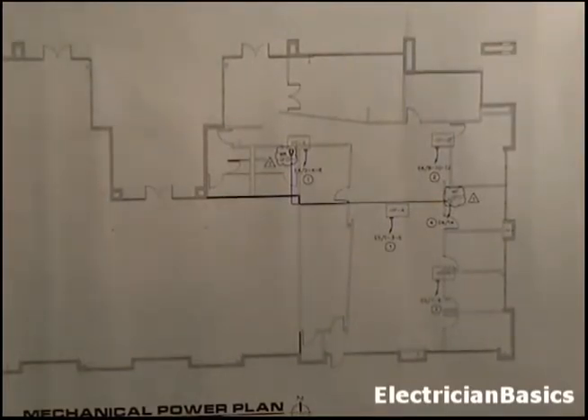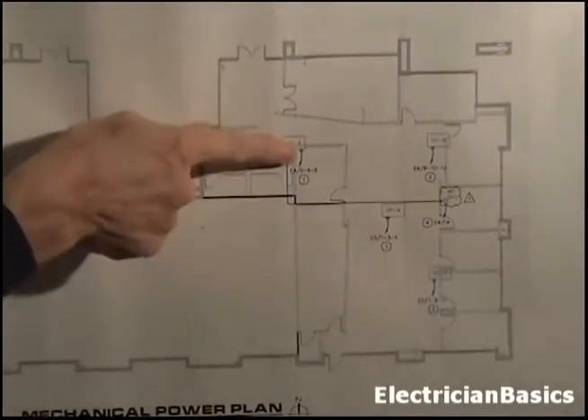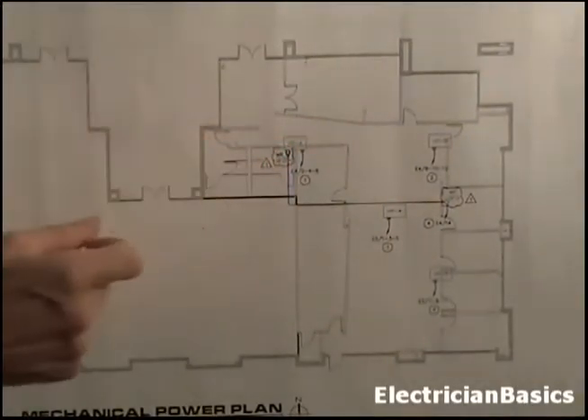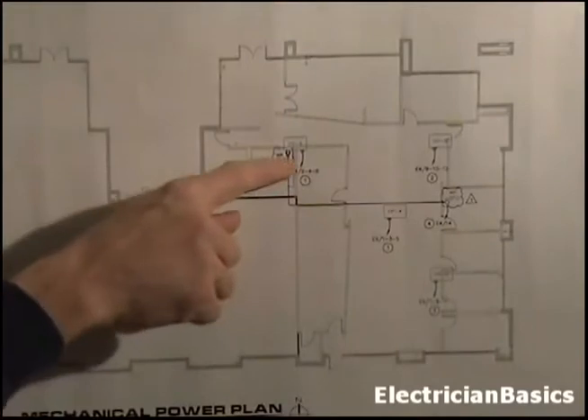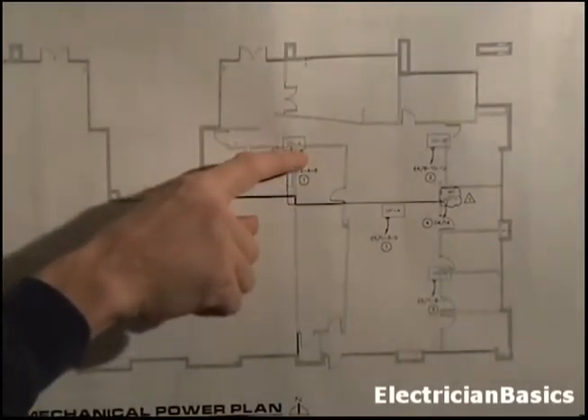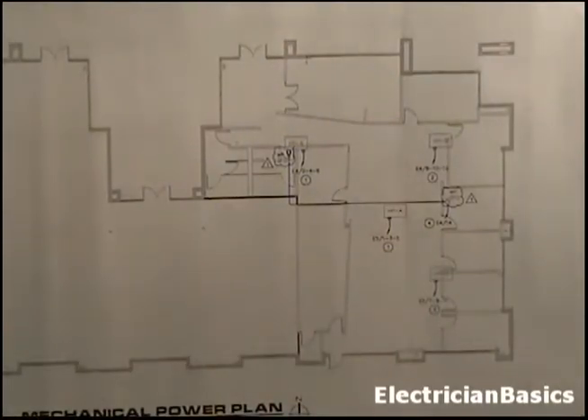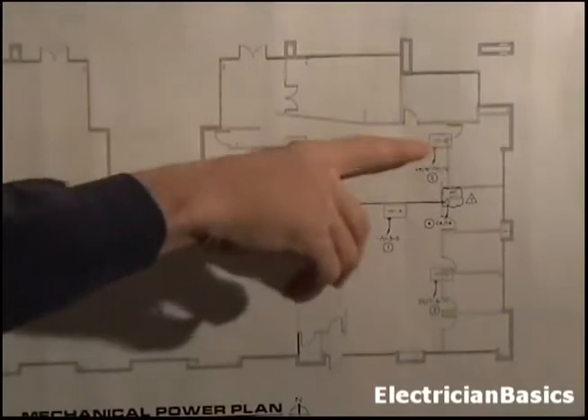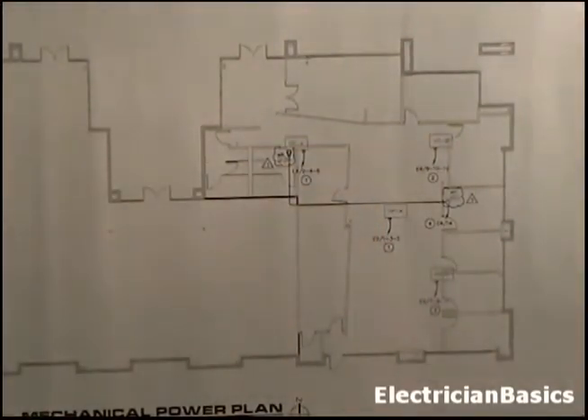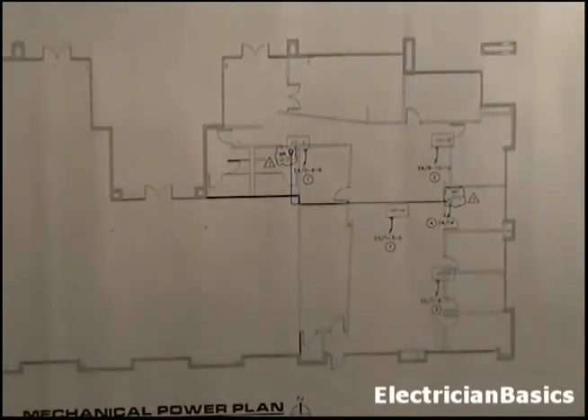Okay, another thing we look to at the heat pumps, you can see, of course, we got the line with the arrow which shows home run. We've covered that symbol before. But there's a little box on the side of each of these where the arrow comes out of. That's where your disconnect goes. On your heat pump, it may not actually be on that side of the heat pump. It just depends on the model. And this is just, again, a symbol that the architect puts on there. So you actually have to look at the heat pump, how it orients on the roof, and put it on appropriately. You can find that information.